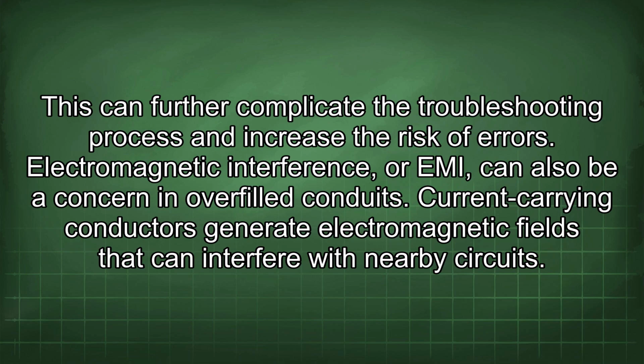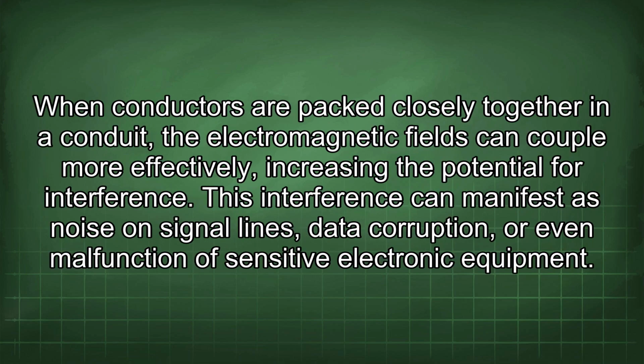Electromagnetic interference, or EMI, can also be a concern in overfilled conduits. Current-carrying conductors generate electromagnetic fields that can interfere with nearby circuits. When conductors are packed closely together in a conduit, the electromagnetic fields can couple more effectively, increasing the potential for interference. This interference can manifest as noise on signal lines, data corruption, or even malfunction of sensitive electronic equipment.